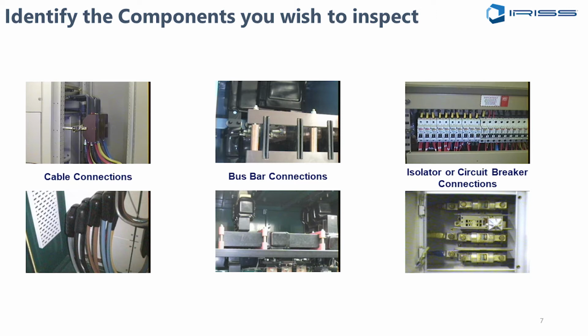As the load ramps up and down and those conductors heat up and cool down, they expand and contract at slightly different rates, which over many weeks, months, and years causes them to get looser. As they loosen, the connection develops higher resistance, which increases the amount of heat given off, in proportion to the current squared, since P equals I squared R. So over time, every electrical connection will, with thermal cycling, slowly get looser.